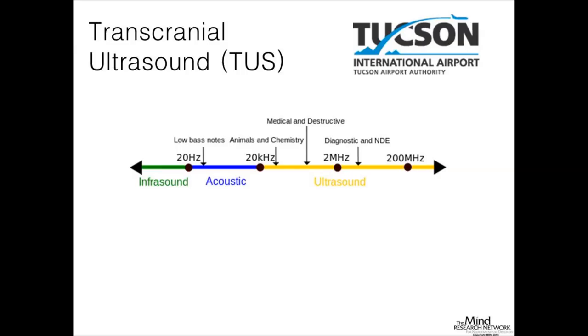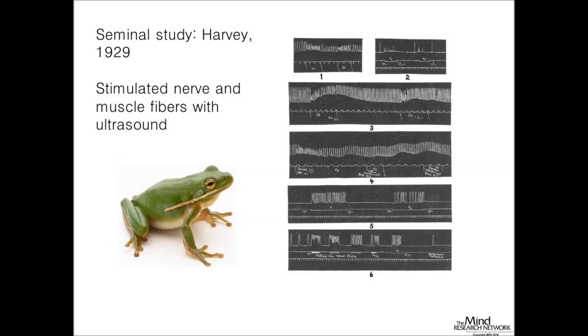I'm going to be talking about ultrasound frequencies that are typically used for medical imaging all across the world. Ultrasound is anywhere above 20,000 hertz—that's 20,000 oscillations a second, above what the human ear can detect. We're talking about frequencies up to about 10 megahertz. Medical imaging is somewhere around 2 to 10 megahertz—10 million oscillations a second. Right off the bat, we're using intensities and power levels that are being used every day for medical imaging.